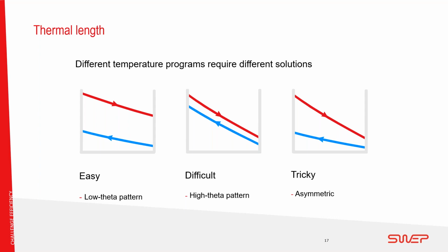Then we move into a more difficult thermal case, which can be covered by a high theta pattern. This would be where we have a large temperature change, but a small temperature difference between the two fluids. And then finally, we may see something more tricky, where the change in temperature on each fluid might be different, and then we have a changing temperature difference between the two sides over the heat exchanger. This can be covered by an asymmetric design, where we would have different theta patterns or perhaps a set of wide and narrow channels.